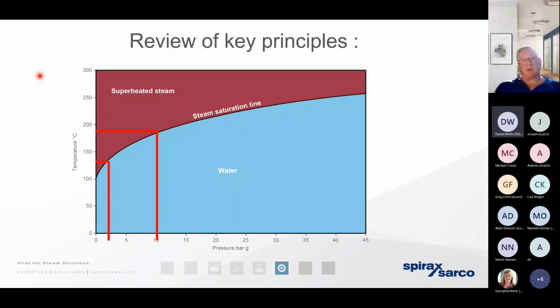It also tells us the importance of having a sufficient number of pressure gauges around the network so we can accurately commission and determine what's happening within the steam system. So this demonstrates the relationship between the pressure and temperature of the steam, but it also shows us the relationship between the pressure and the temperature of the condensate itself. And that's important to understand because when the steam gives up its heat energy, that's the useful heat energy demonstrated in that box in blue on the previous slide. When the steam gives up that useful heat energy, it condenses, changes state from a gas to a liquid, and the liquid condensate retains the sensible heat. It retains the heat that is unable to be imparted to the process.